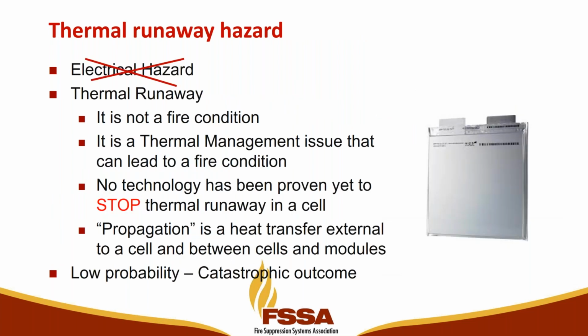So what we look at from thermal runaway is it's not an electrical hazard, it's not a fire condition - it is a thermal management issue that can lead to a fire condition. Right now there's no technology once a battery has started moving into thermal runaway - it's basically shorting out internal to the battery, and you can't stop it. So what I want to define is: thermal runaway is internal to a battery, propagation is what we call external. That's different than fire propagation, but it is propagation of heat transfer between cells to modules, between modules to racks, etc. Keep in mind, this is still a very low probability event, but unfortunately the outcome can be very catastrophic in the consequences of failure modes.